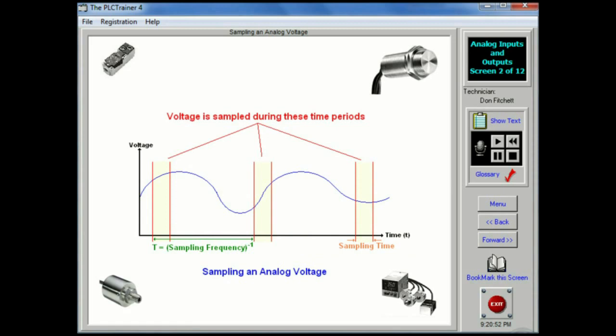AD converters can only acquire a limited number of samples per second. The time between samples is called the sampling period T, and the inverse of the sampling period is the sampling frequency, also called the sampling rate. The sampling time is more often much smaller than the sampling period. The sampling frequency is specified when buying hardware, but for a typical PLC, a maximum sampling rate might be 20 hertz.